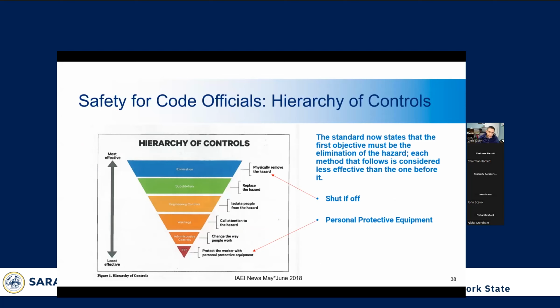All right, so here we have the hierarchy of controls. This is a method of evaluation and selecting the most appropriate method of protection for personnel. The best control is always elimination of the hazard, as you can see here. That's basically shutting off the power to the solar PV system. If you have to check the connections for the inverter on the solar system, make sure they're tight. You want to shut the system down so that there's no power in those wires. And if you're testing to make sure that the connections are tight, you don't potentially pull it out and electrocute yourself. The next best is replacing the hazard.